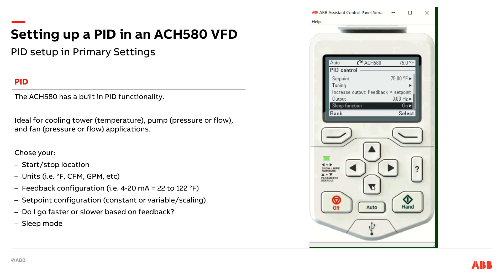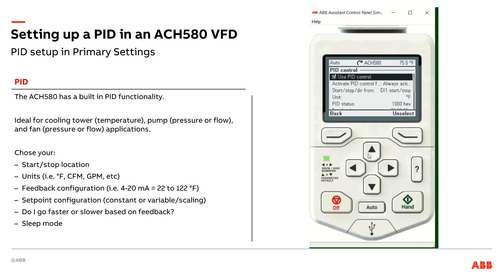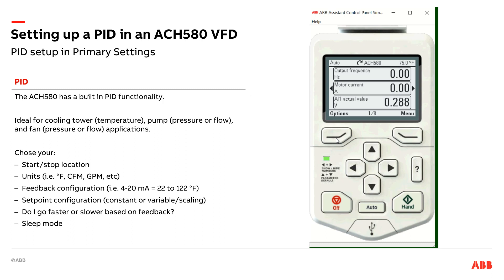So there you have it — setting up a PID control on the ACH 580. One other neat thing: if I come all the way back to the home view and hit the left arrow, you can see that it's already set up for PID. I've got my cooling tower set point at 75 degrees, my feedback right now is 79 degrees, and I'm not running. It's a little quieter when I do this when the equipment's not actually running. So there you have it — how to set up a cooling tower PID on the ACH 580. Thank you.